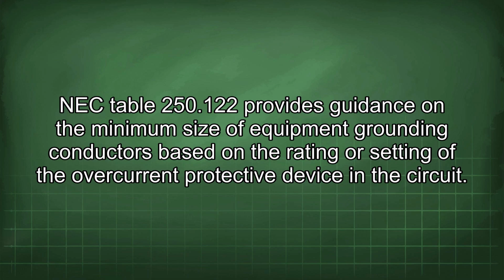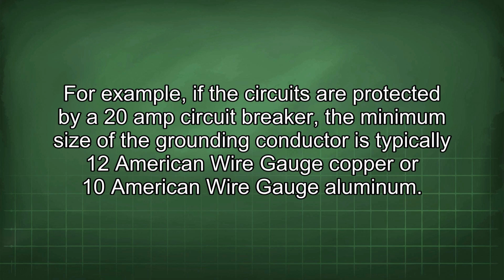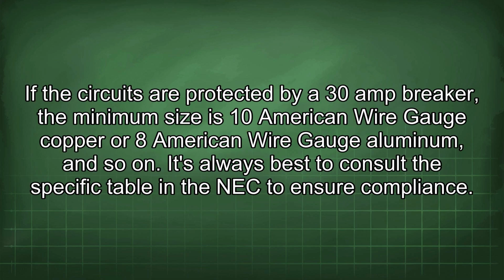NEC Table 250.122 provides guidance on the minimum size of equipment grounding conductors based on the rating or setting of the overcurrent protective device in the circuit. For example, if the circuits are protected by a 20 amp circuit breaker, the minimum size of the grounding conductor is typically 12 American wire gauge copper or 10 American wire gauge aluminum. If the circuits are protected by a 30 amp breaker, the minimum size is 10 American wire gauge copper or 8 American wire gauge aluminum, and so on. It's always best to consult the specific table in the NEC to ensure compliance.